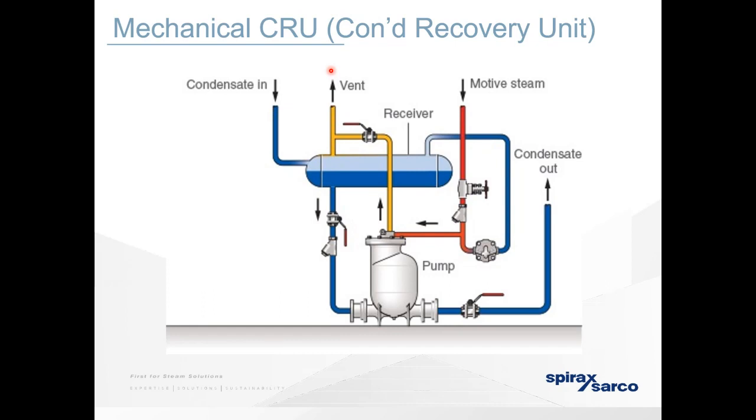If you talk purely by material, not cost, stainless steel is always going to be the better material. It's harder, it wears less, it's not prone to corrosion, as you said, so you won't see the rust. But it is expensive. So a way to lower costs, if stainless steel piping is something you would like, is by increasing the pressure, because then you lower the volume.